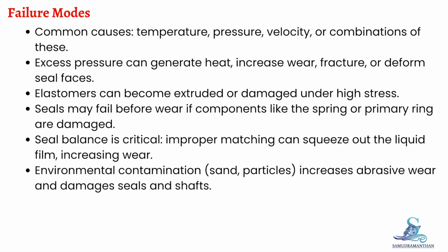Failure modes. Mechanical seals can fail due to temperature, pressure, velocity, or a combination of these factors. High fluid pressure can create excessive heat, leading to wear, material fracture, deformation, or leakage. Elastomer components may become extruded or damaged.